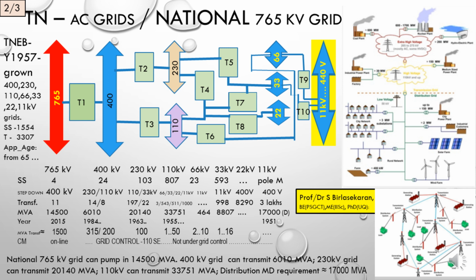And 66 kV transports only about 464 MVA, and 33 kV transports about 8,807 MVA. The 22 kV bus is mainly intended for industrial uses, and the 11 kV 400 volts pole mounted transformers running to about 3 lakhs are the final reaching point of customers demanding about 17,000 MVA. The oldest transformer in that is somewhere installed around 1951. The two right-hand slides show the typical grid system used overseas.